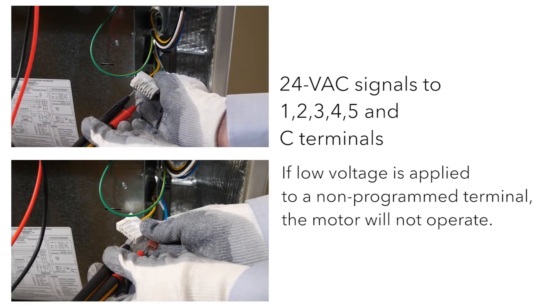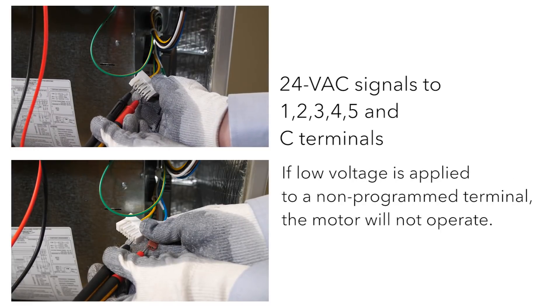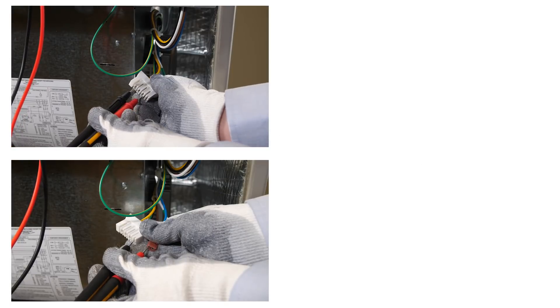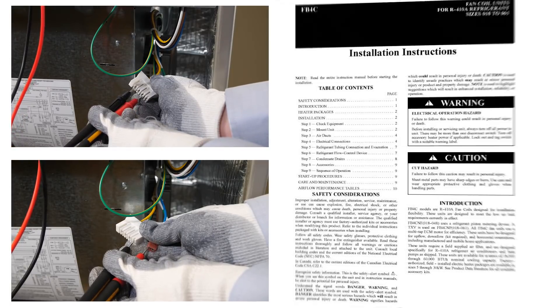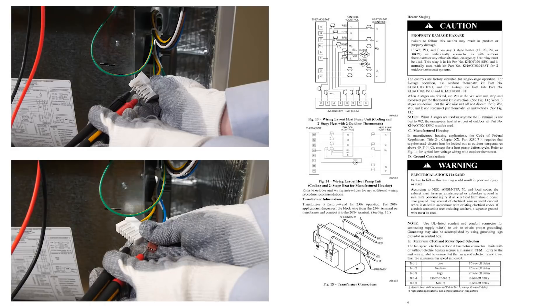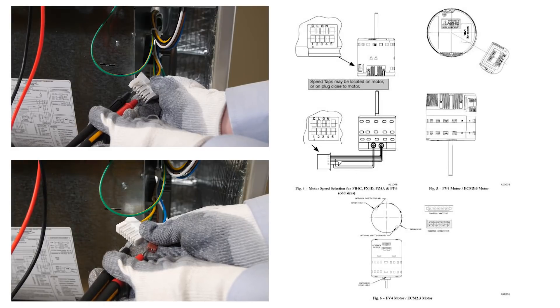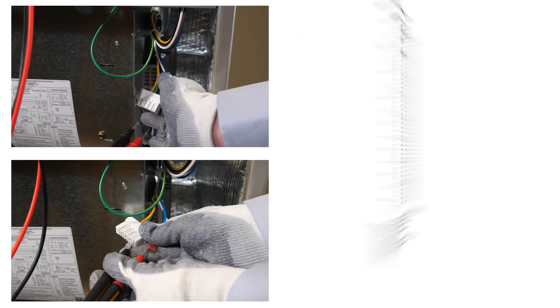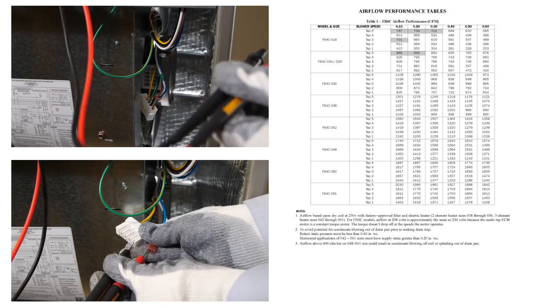Not all taps are programmed. If low voltage is applied to a non-programmed terminal, the motor will not operate, which is normal. Check the published literature of the unit for airflow delivery tables to see which speed taps are programmed. If there are any voltage issues at this point, you'll need to correct them before proceeding to the next step.